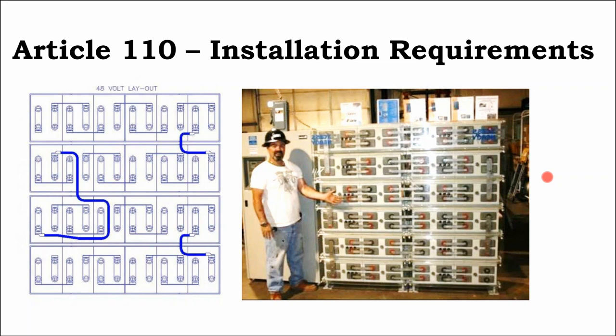And for reasons we get into in the battery class, the fact that unsealed batteries can emit gas also means you can charge them and discharge them a little bit harder. And in maintenance cycling of batteries, if you can apply a very hard charge to the battery, it can actually clean them. So when you're cleaning your unsealed lead acid batteries, you're applying a high voltage to them to condition them a little bit better.